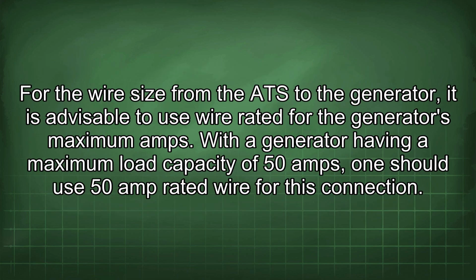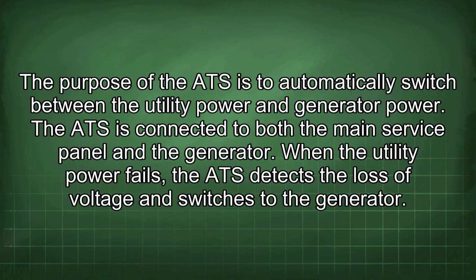For the wire size from the ATS to the generator, it is advisable to use wire rated for the generator's maximum amps. With a generator having a maximum load capacity of 50 amps, one should use 50 amp rated wire for this connection. The purpose of the ATS is to automatically switch between the utility power and generator power.